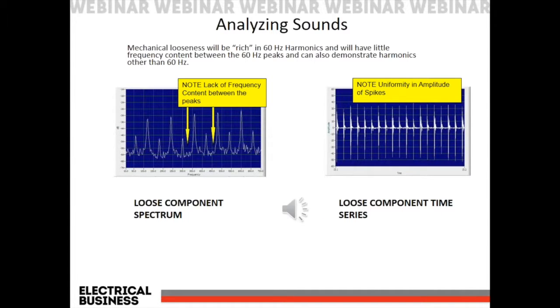Then the next one here is where we have a mechanical vibration. I showed you a couple slides back that corona had a 60 hertz harmonic showing up, but also had content in between. If you look at the spectrum on the left side here, we have 60 hertz, and even though I didn't mark them off, our 120s are more dominant, but still giving us a 60 hertz harmonic. But note the lack of frequency content in between the peaks. There is no content like we saw with corona or an electrical discharge. And that's our indication right there to say this is a mechanical vibration. And this is one example of a mechanical vibration sound.